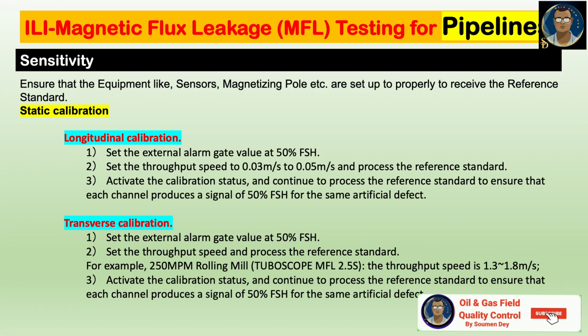Okay. There are different types of calibration. One is static calibration, another is dynamic calibration, and there will be calibration also before we start the examination or the actual MFL detection. Static calibration has two types: longitudinal calibration and transverse calibration. During longitudinal calibration, you can set the alarm gate value at 50% FSH, set the throughput speed to 0.03 meter per second to 0.05 meter per second, and process the reference standard.